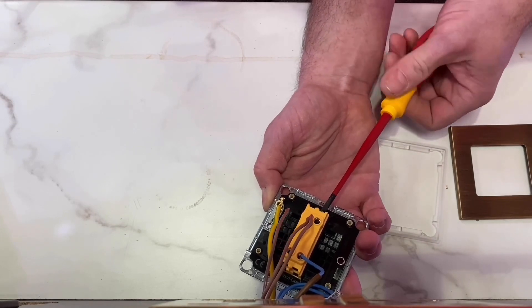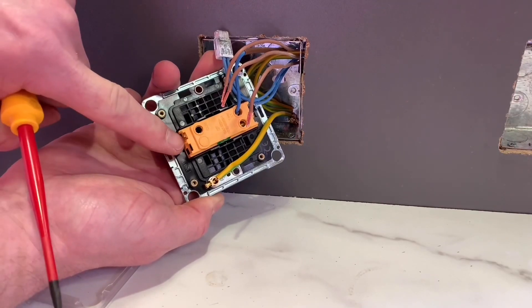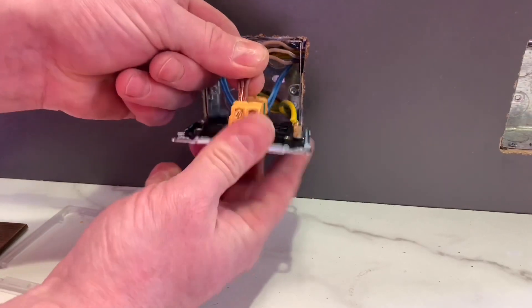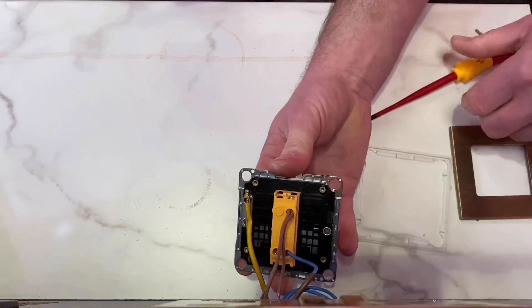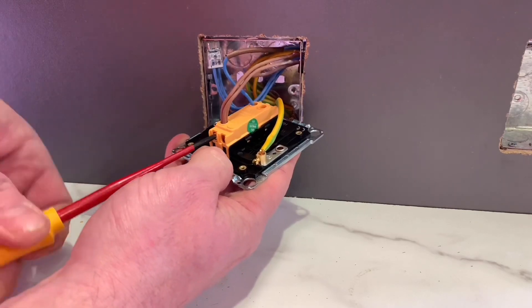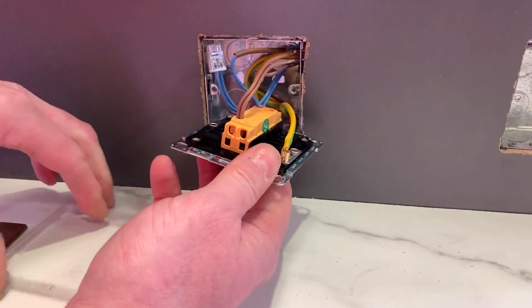When I back off the screw, it gets stiff at the point that I'm fully opened, so you're not going to risk that screw dropping out onto the floor. And they've identified for me — it's a two-way switch being used as a one-way — they've actually identified the terminal in the switch that is for the one-way as well, so there's no guessing for the electrician. That's a handy feature. Tighten this back in — three doubled-over cables went in no problem.